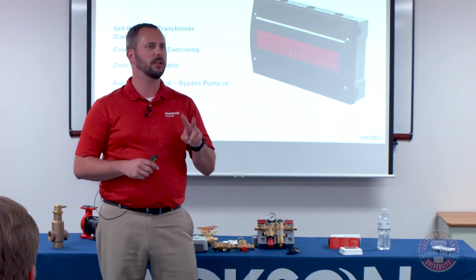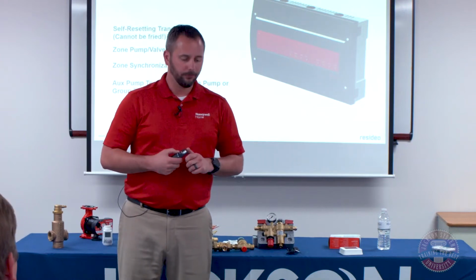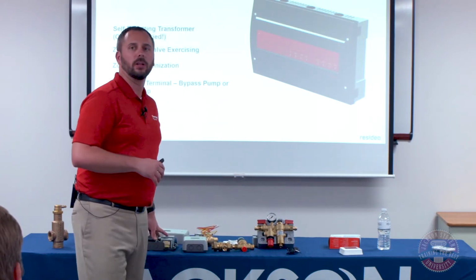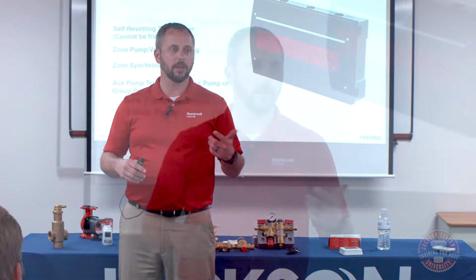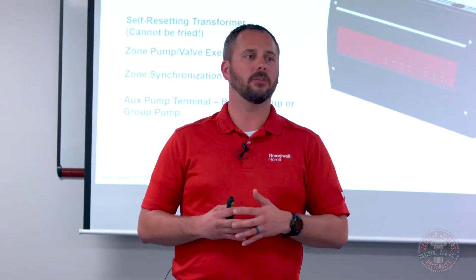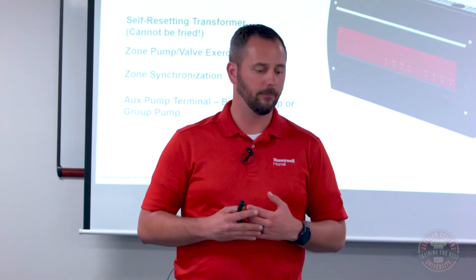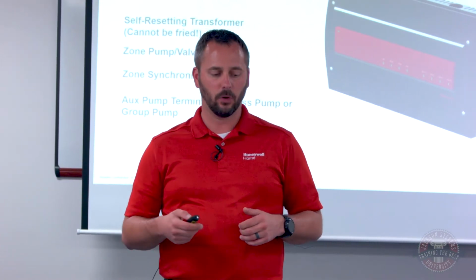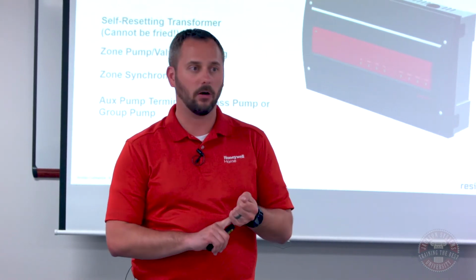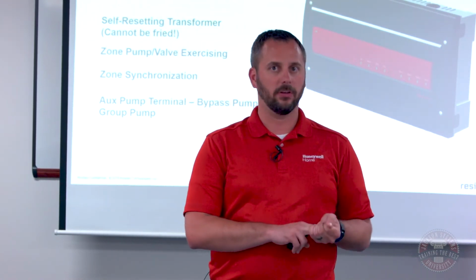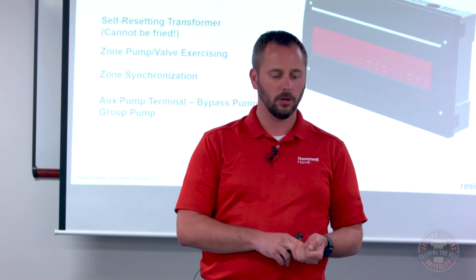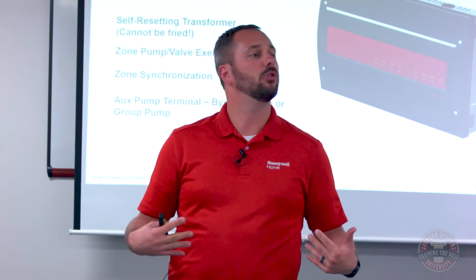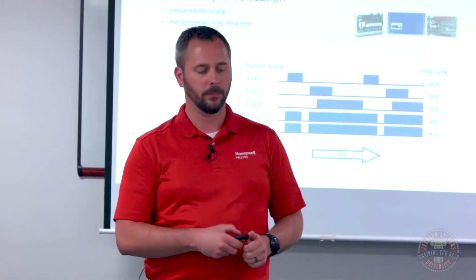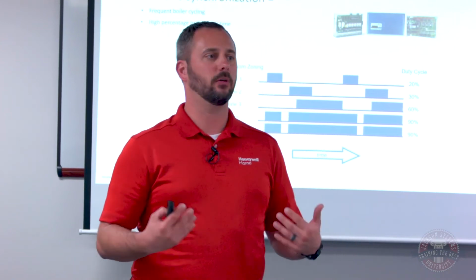Another series of products that we have had for a while, and I'm going to touch on 2 big pieces with this, is our Aqua controls. These are really neat controls because this is really just a simplistic relay that simplifies the wiring and lets you know what's going on. You've got LED diagnostic lights. This adds some actual logic and brains into the system. It has a self-resetting transformer, gives you the ability to do pump and valve exercising, and gives you zone synchronization, which I will touch on because that's a pretty big deal. It's also got some additional terminals where you can do some more stuff with it, depending on what you're trying to do in the system. But one thing I want to touch on is what zone synchronization is.